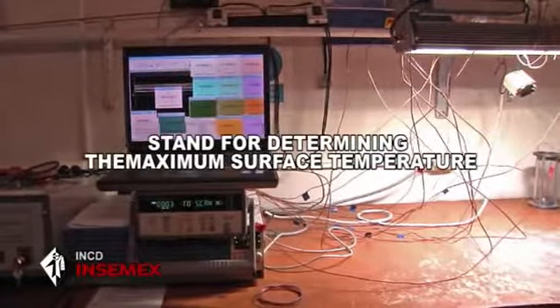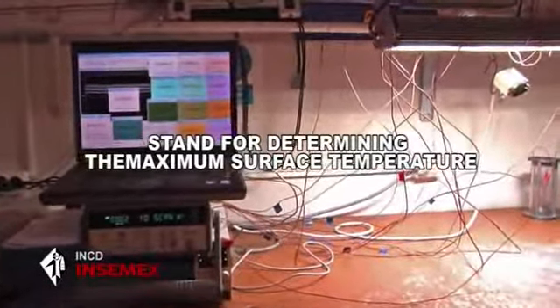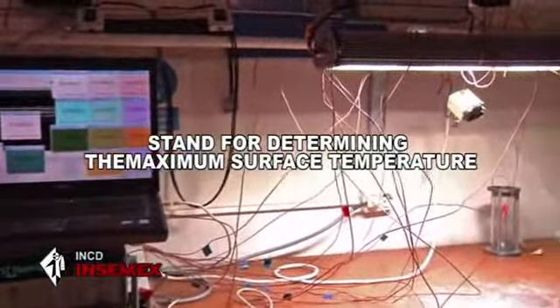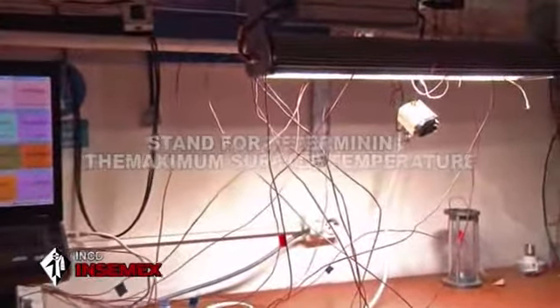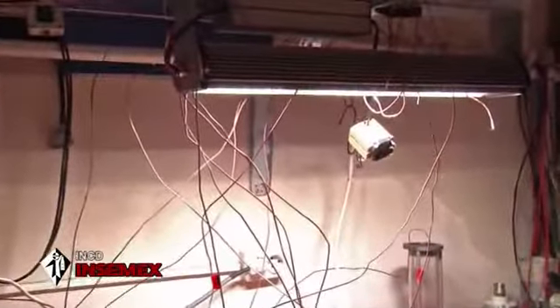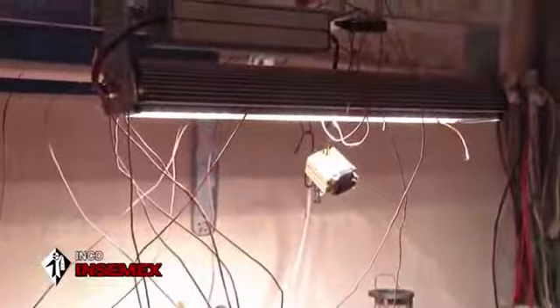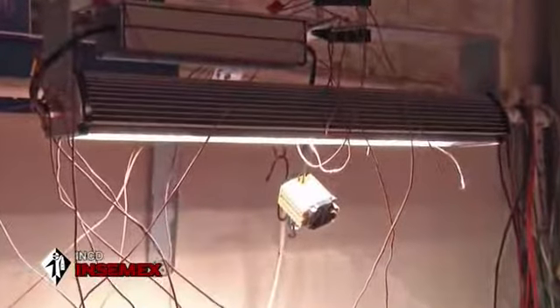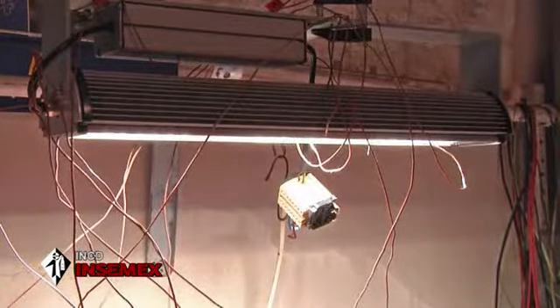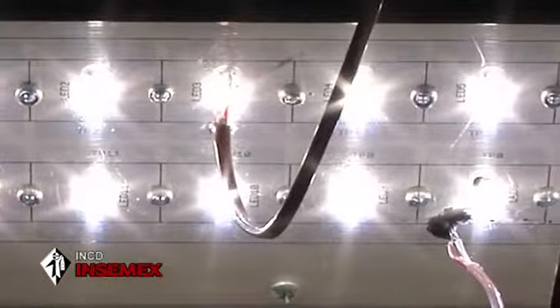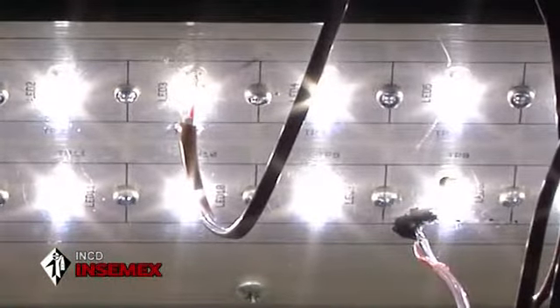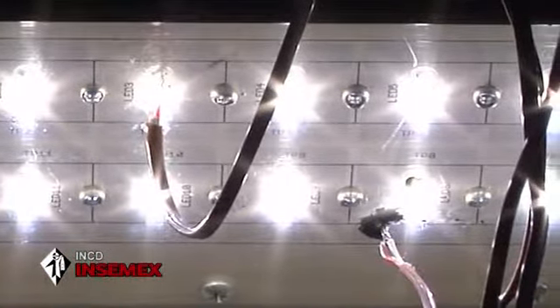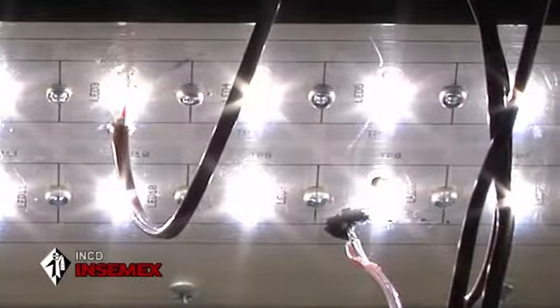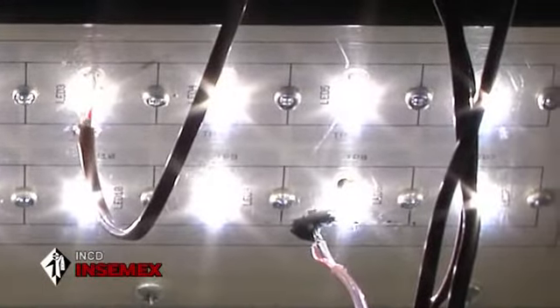Stand for determining the maximum surface temperature. The stand for determining the maximum surface temperature is used for measuring the maximum surface temperature of explosion-proof electrical equipment with flame-proof enclosure type of protection and increased safety type of protection, with a maximum power of 1 kVA.